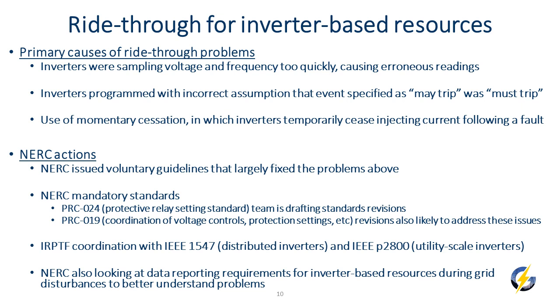So through the guideline process, NERC has gotten the vast majority of the inverter industry and the solar industry to adopt these changes. Particularly through the PRC-24 standard, which governs protective relay settings, there's a drafting team currently working on revisions to clarify these issues and make clear that mandatory NERC standards specify you're expected to remain online during these disturbances, clarifying some of the other confusion that caused these events.